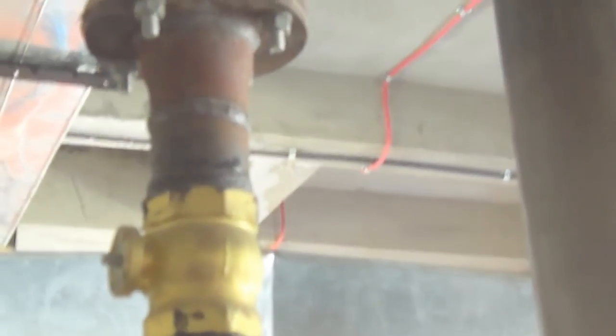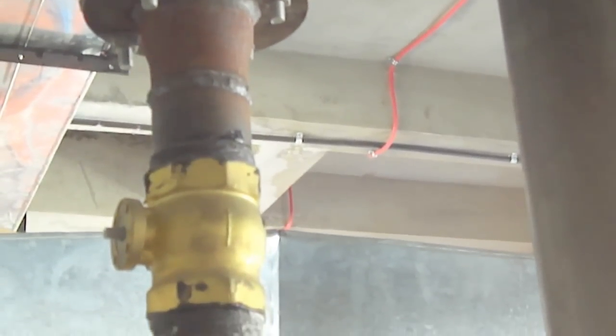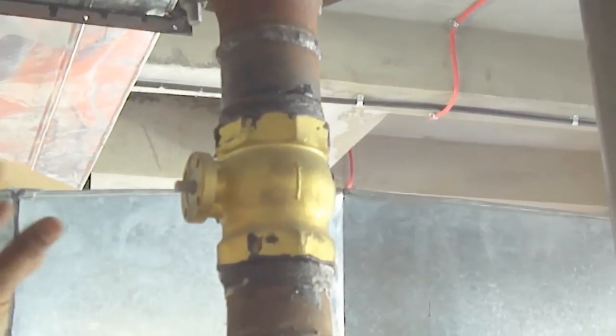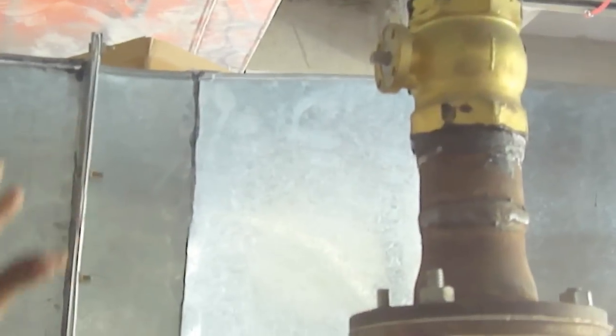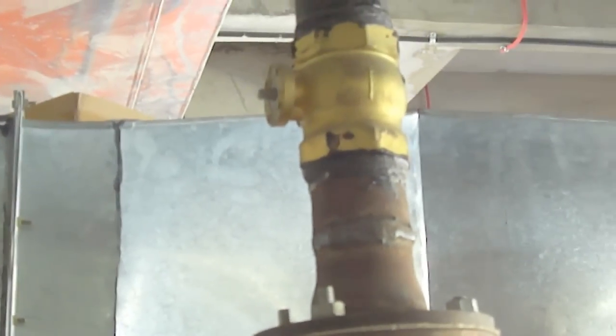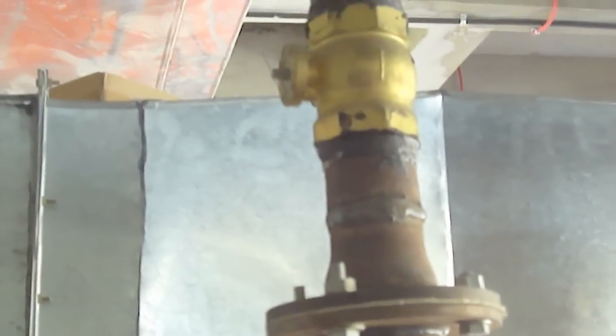So two-way means that it is for variable flow. So automatically it will increase. Here you will find one control actuator, a controlling device, and that will control as per the sensor or as per the thermostat of the AHU. And when it attains the required temperature, it will set to minimum.